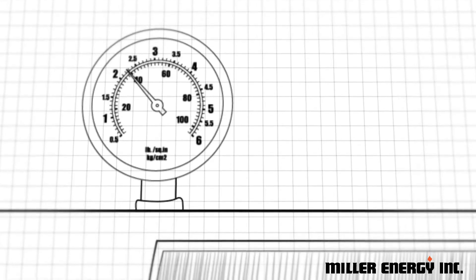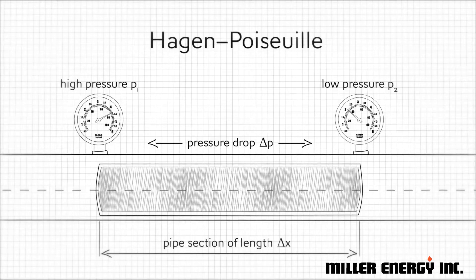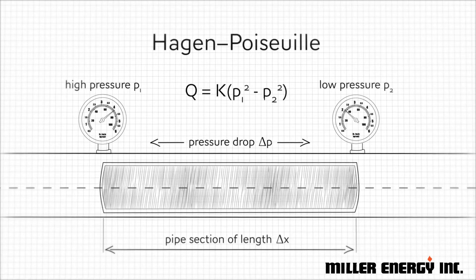By measuring the upstream pressure and downstream pressure across a laminar flow element, this equation can be used to relate these measured pressures to the actual mass flow.